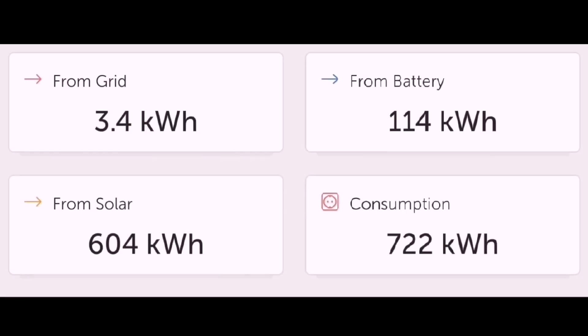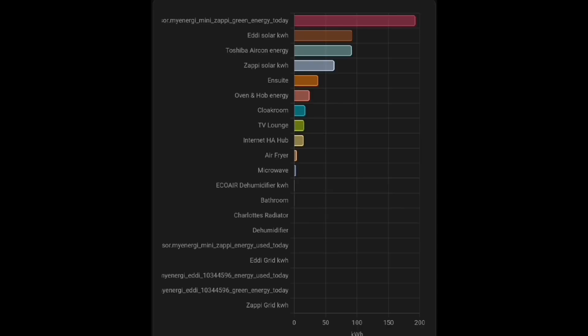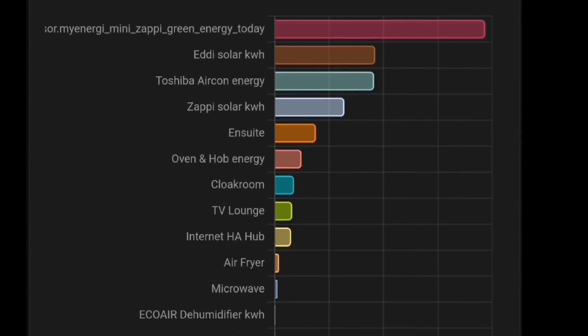The Victron inverter data shows grid usage of only 3.4 kWh — slightly lower than the Octopus figure — and interestingly, none of that grid energy went into the battery. Looking at where all our generated energy went: Victron shows we consumed 722 kWh total — 604 kWh came from solar, 3.4 kWh from the grid, and 114 kWh from the battery. Hot water heating via the Eddi device used 92.4 kWh, all from solar with no grid import overnight. The Zappi EV charger used 265 kWh with no overnight grid charging, and the house itself consumed 409.8 kWh.